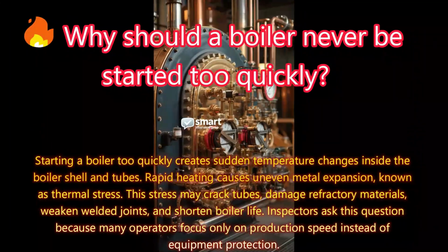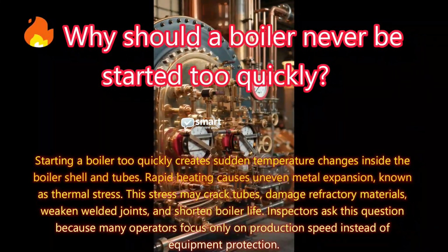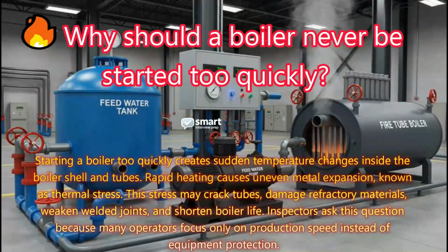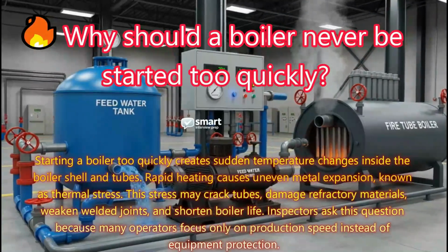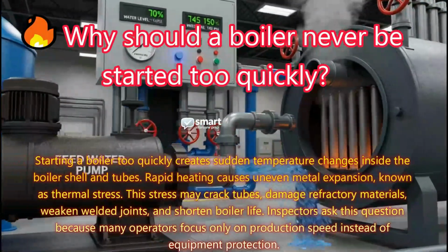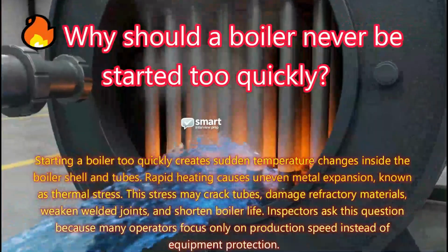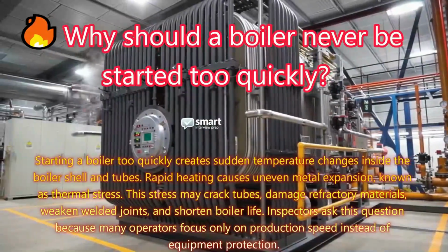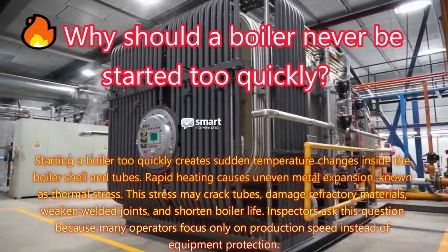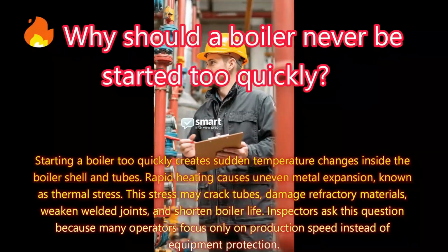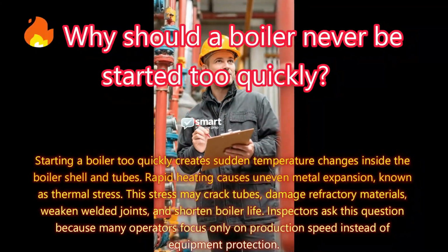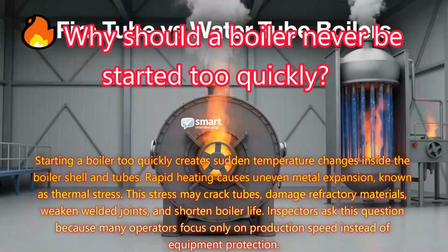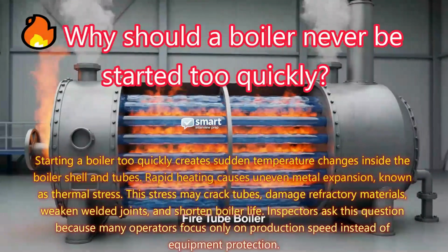Answer: starting a boiler too quickly creates sudden temperature changes inside the boiler shell and tubes. Rapid heating causes uneven metal expansion, known as thermal stress. This stress may crack tubes, damage refractory materials, weaken welded joints, and shorten boiler life. Inspectors ask this question because many operators focus only on production speed instead of equipment protection.